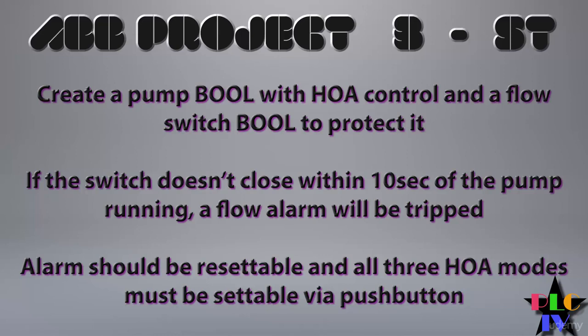What we're also going to have to protect our pump is a flow switch. So once the pump comes on, after 5 seconds, if the flow switch hasn't closed, that's going to mean that our pump is pumping, but there's nothing flowing through the pipe, which means we've got a problem because that pump's about to burn itself up.